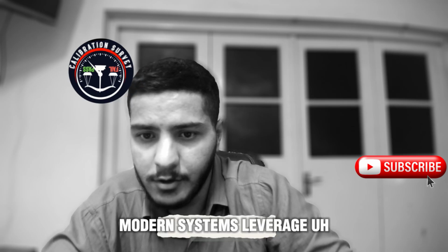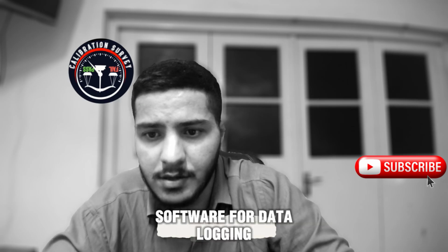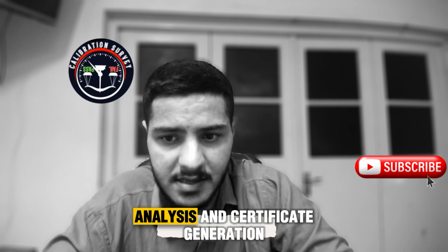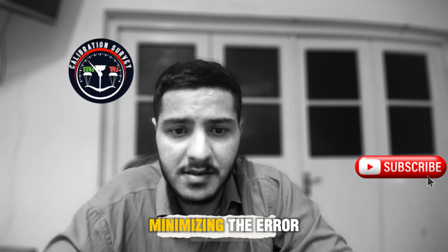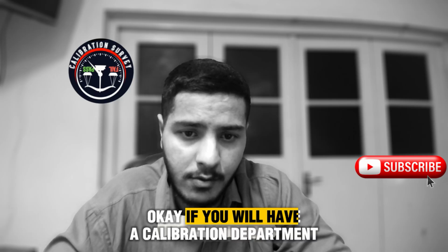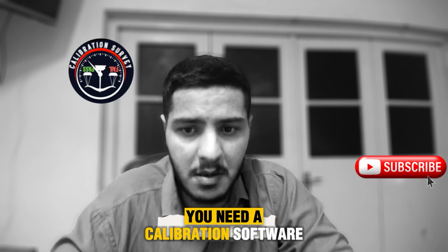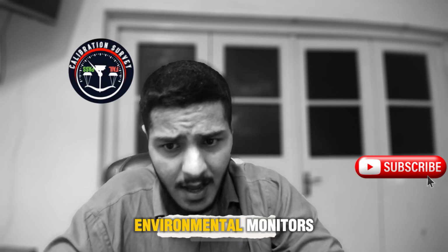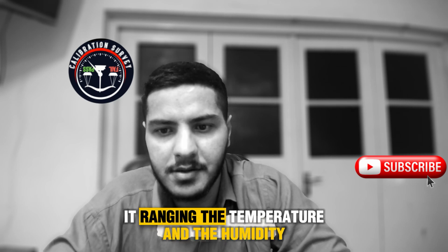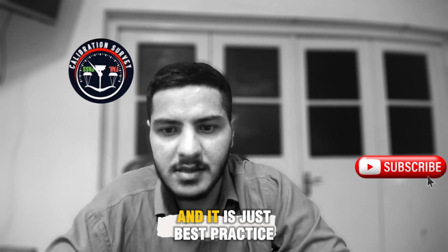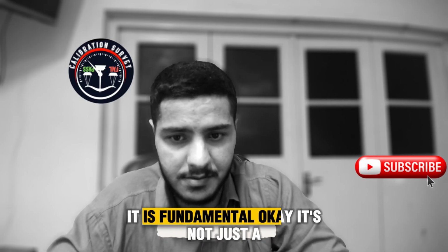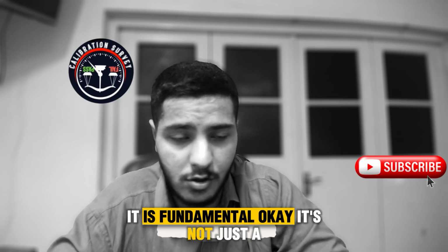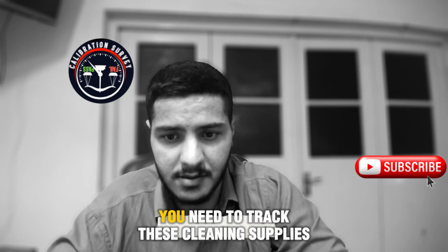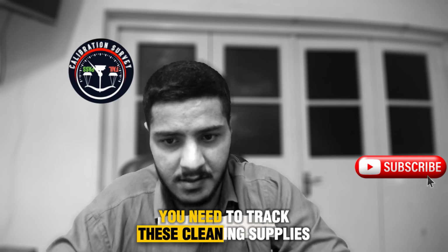Calibration software. Modern systems leverage software for data logging, analysis, and certificate generation, minimizing the error. Okay, if you will have a calibration department, you need calibration software. Environmental monitors, tracking the temperature and the humidity. It is fundamental. Okay, it's not just best practice. You need to track these.